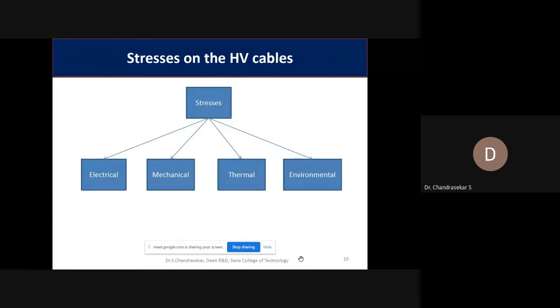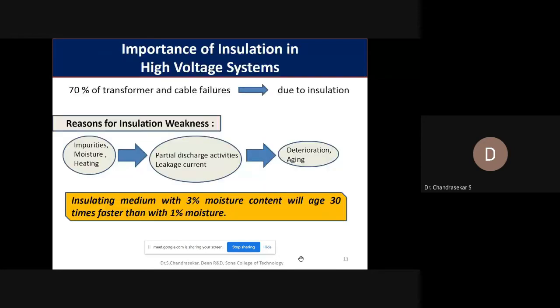In the case of cables also, we can see there are so many stresses, the same types we already discussed for transformers: electrical stresses, mechanical stresses, thermal stresses, and environmental stresses. Here, environmental stresses means the humidity or moisture content in the soil, which can ingress into the material and slowly degrade the quality of the solid insulation. Mechanical stresses normally happen during bending, and electrical stresses, as you know, are due to over voltages, switching over voltage and lightning impulse over voltage. So these are all the various stresses normally experienced by underground cables.